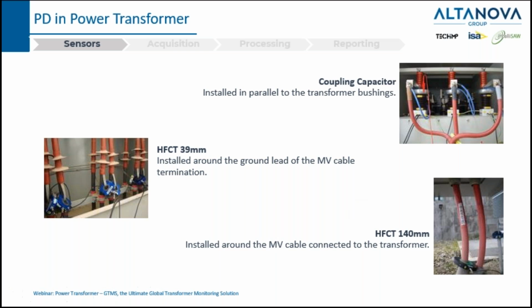Here are examples of sensors that we also use normally in a medium voltage transformer. Basically, they are coupling capacitors installed in parallel to the transformer bushings, or other types of high frequency current transformer installed around the ground lead of the medium voltage cable, or around the cable itself when the ground lead is not available.